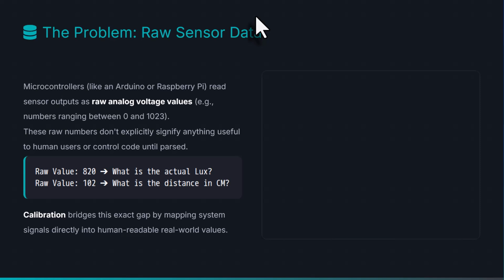For example, a raw value of 820 tells us about the actual lux, and a second raw value of 102 tells us the distance in centimeters. So calibrating bridges this exact gap, mapping system signals directly into human-readable real-world values.